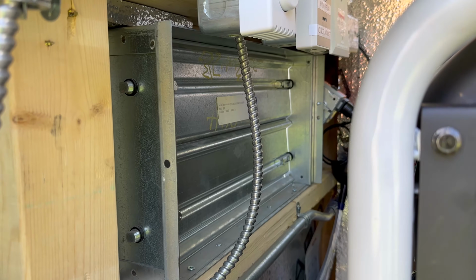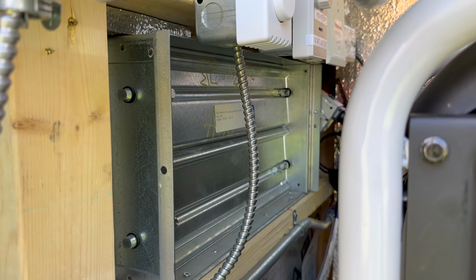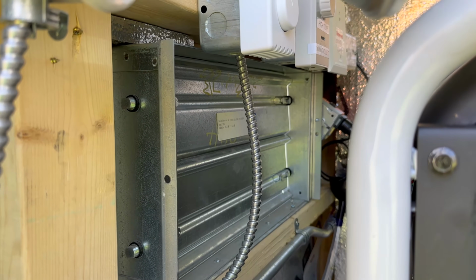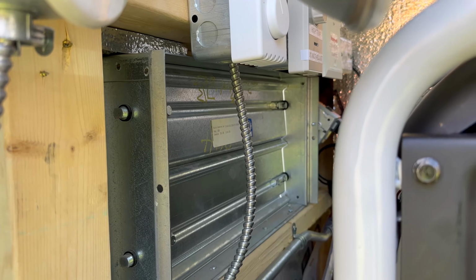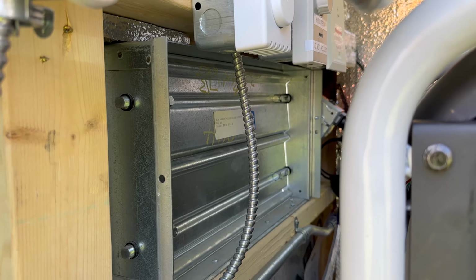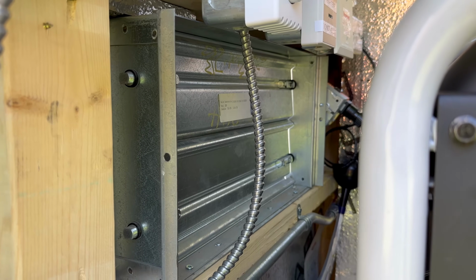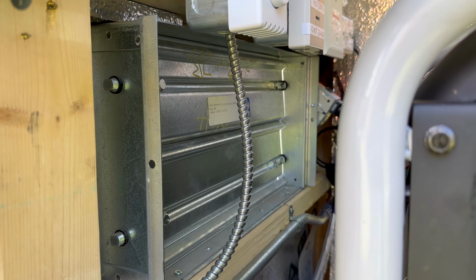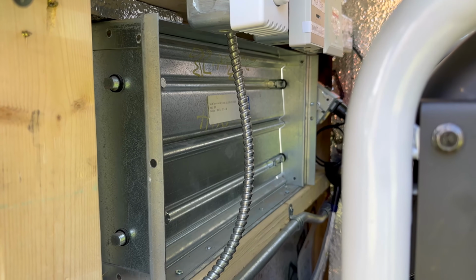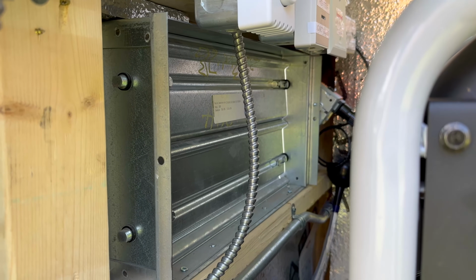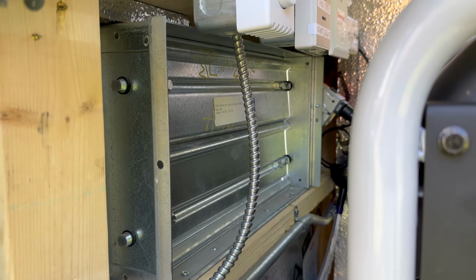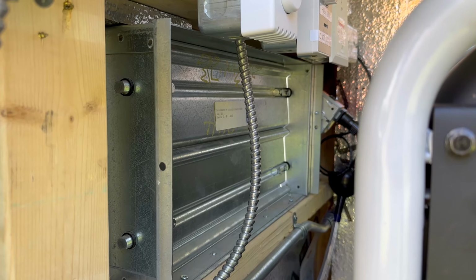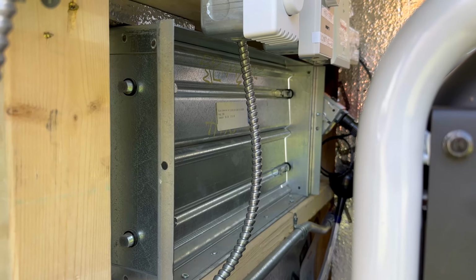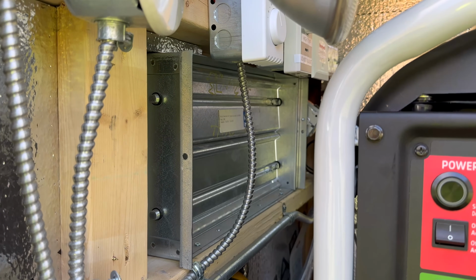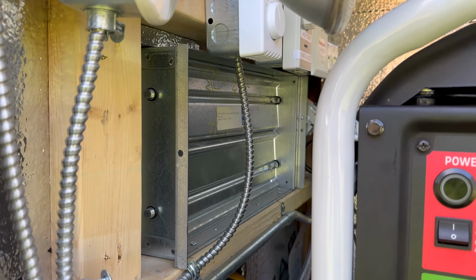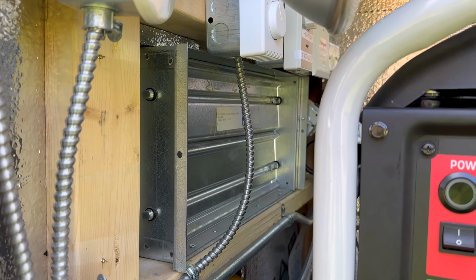How the damper works, it's a 3-wire system where if it has 24 volts on 2 of the wires, it will go to fully close, and the 3rd wire determines how far open it is if that wire has a voltage applied to it. For example, if it has 5 volts on that 3rd wire, that will open the damper to exactly halfway position, and if it receives its full 10 volts, it will go all the way open, which is how I have it configured to either be all the way closed or all the way open. So currently this has just 24 volts and 0 volts on the 3rd control wire.